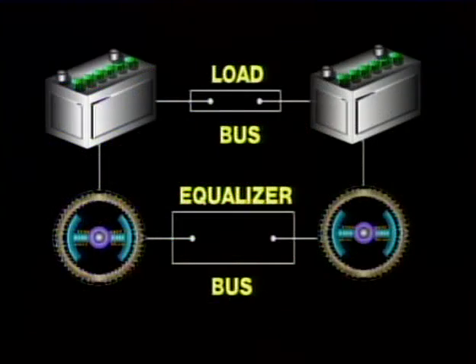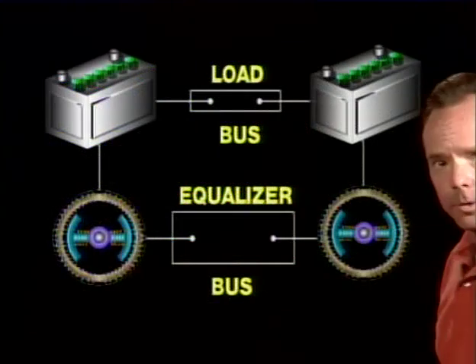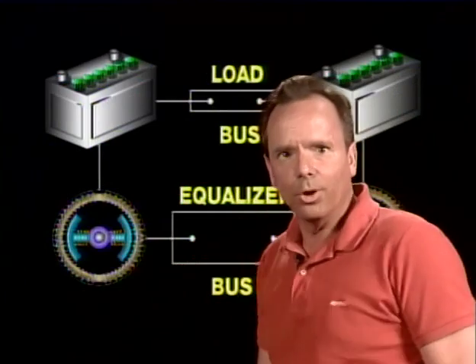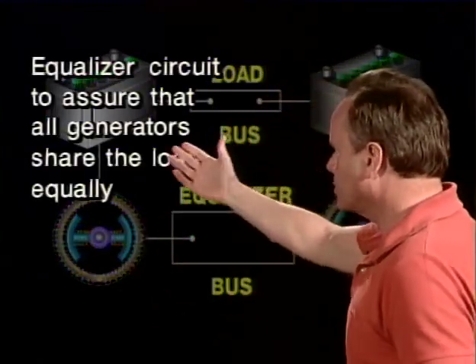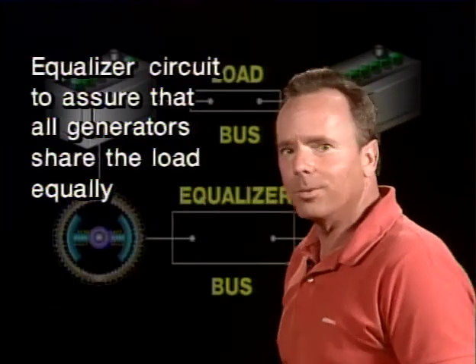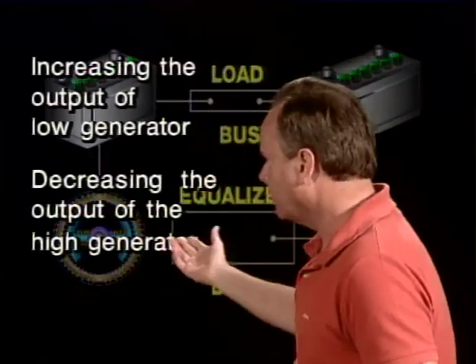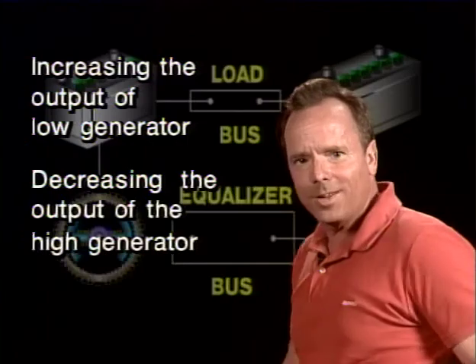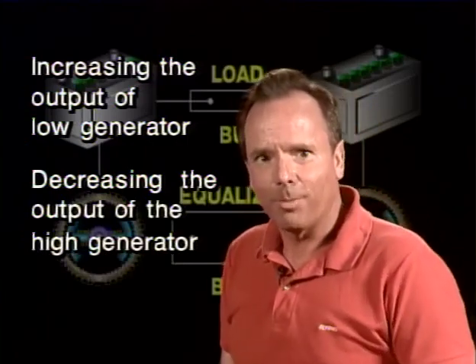Now, when DC generators are operated in parallel to supply power for a single load, their controls include an equalizer circuit to assure that all generators share the load equally. So you do have an equalizer circuit. Now the equalizer circuit operates by increasing the output of the low generator and decreasing the output of the high generator until they're about equal.